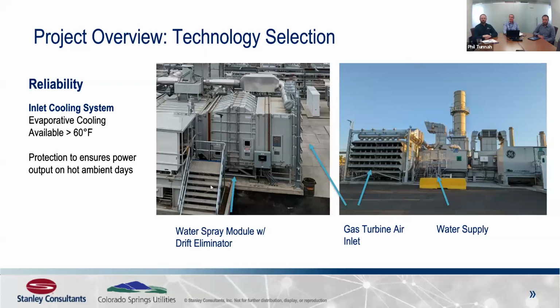With this inlet cooling system, which in this case was evaporative cooling, Colorado's very dry, low humidity environment is well suited for it — spraying water into the inlet and evaporating to lower the temperature. This gives denser air through the turbine, allowing more megawatts through combustion. It's a nice reliability boost on those peak days when you need every megawatt you can get.